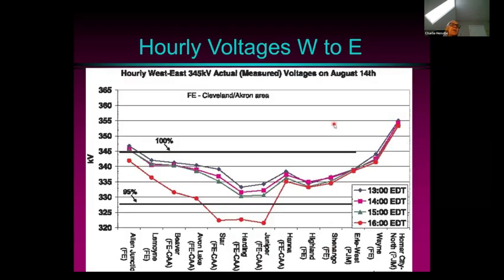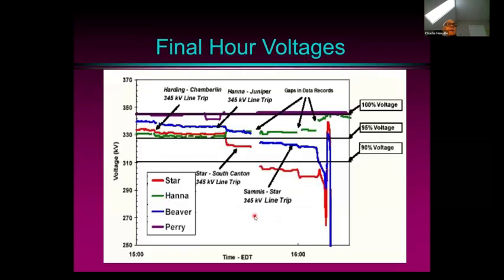And we see the measured voltages just before and during this blackout. You can see this is 95% of nominal voltage, and only at one station did the voltages drop below the 95% mark. So again, the edge of the precipice was not very easily seen just by measuring voltage. And here we have some voltages at various locations just before the blackout. These are various substations in the network, and we can see how they're above 95% of nominal at most locations until very close to the limit or to the end.